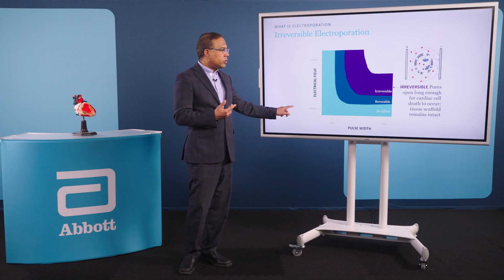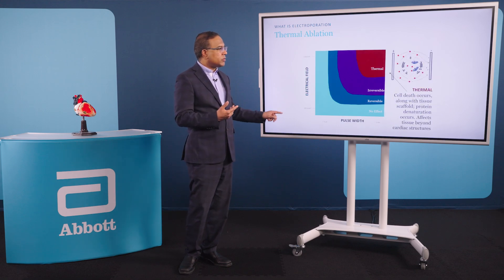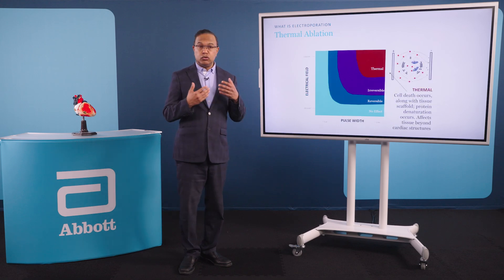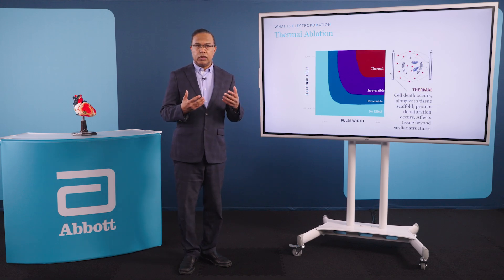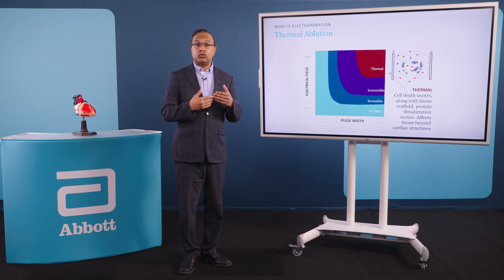However, if we start to turn up the field too much and deliver it over too long a period of time, then we're going to start to get thermal effects, in which case PFA would be no different than radiofrequency or cryoablation.